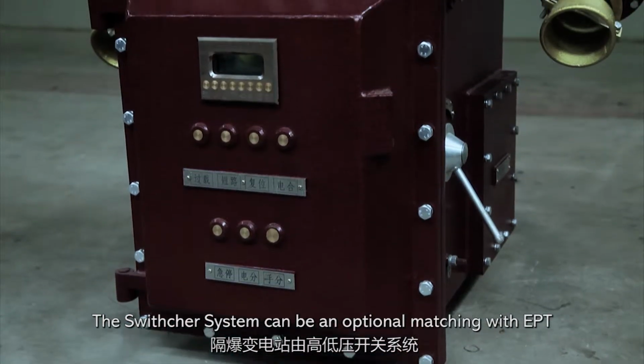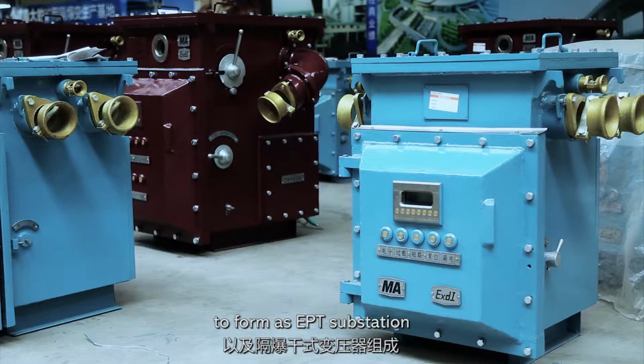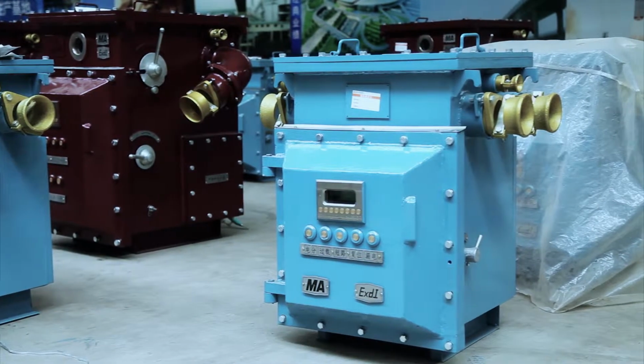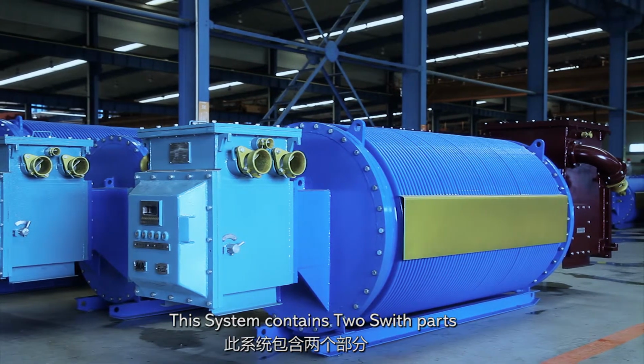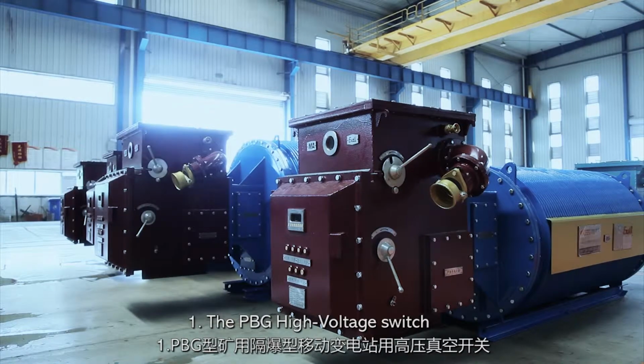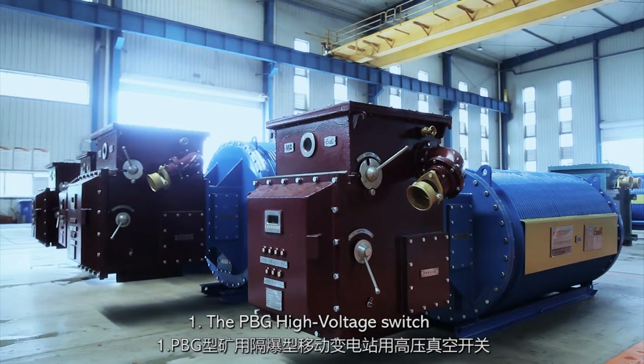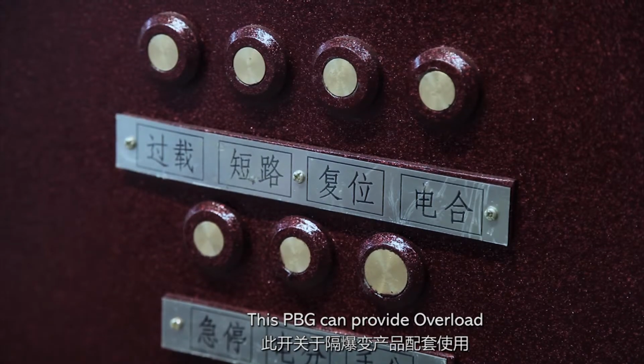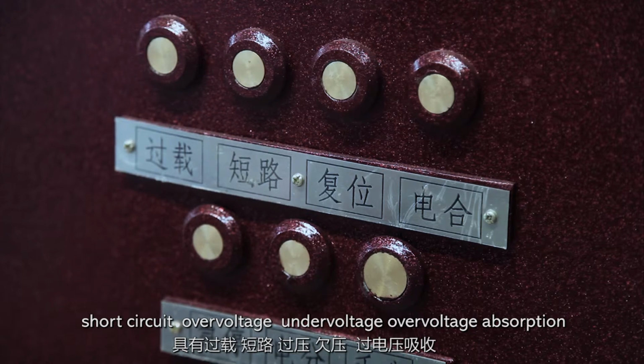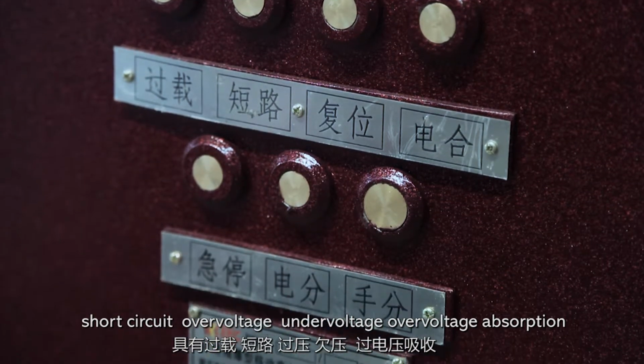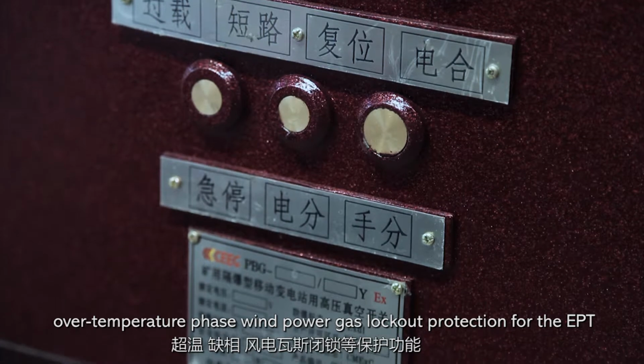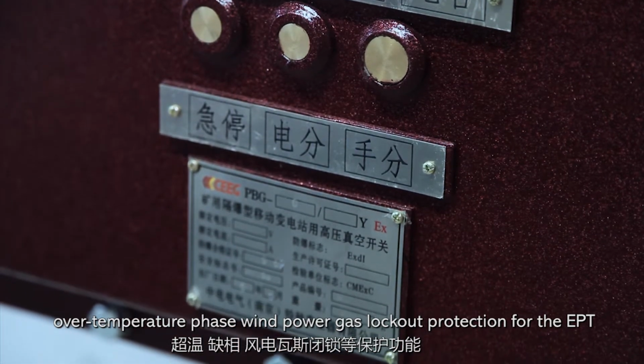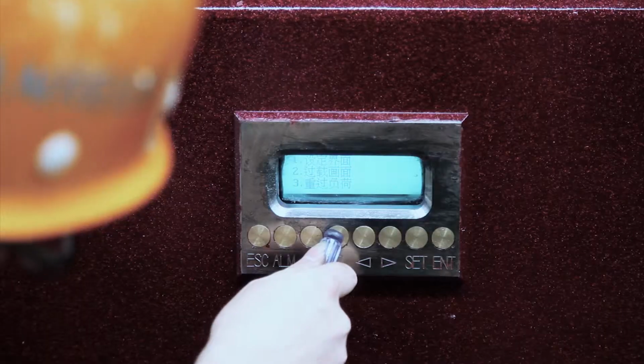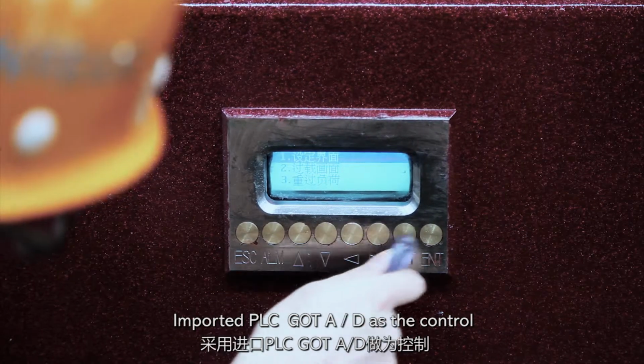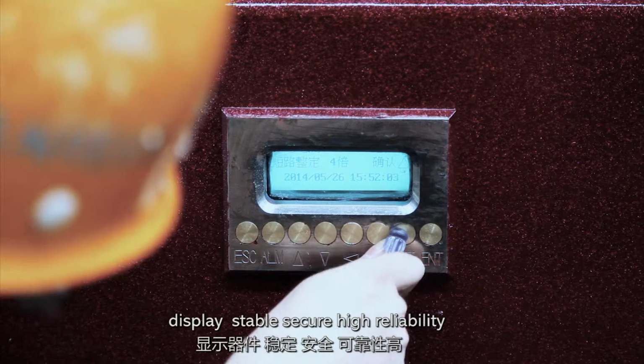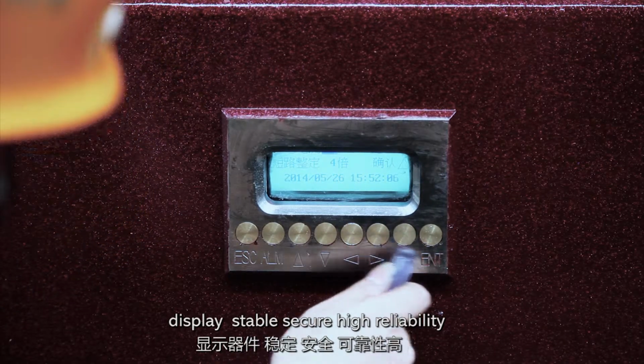The switch system can be optionally matched with the EPT to form an EPT substation. This system contains 2 switch parts. 1. The PBG high voltage switch. This PBG can provide overload, short circuit, overvoltage, undervoltage, overvoltage absorption, over temperature, phase, wind power gas lockout protection for the EPT. Imported PLC, GOT, AD are used for control and display, stable, secure, and highly reliable.